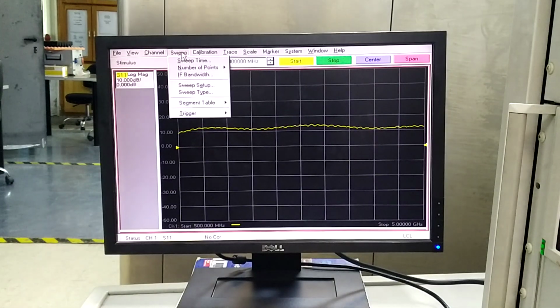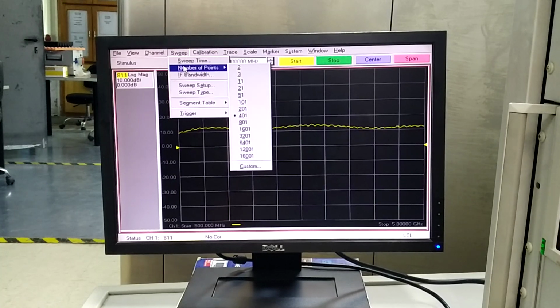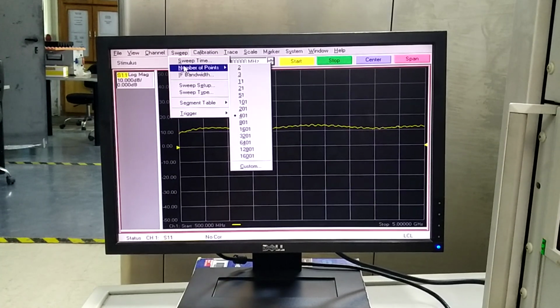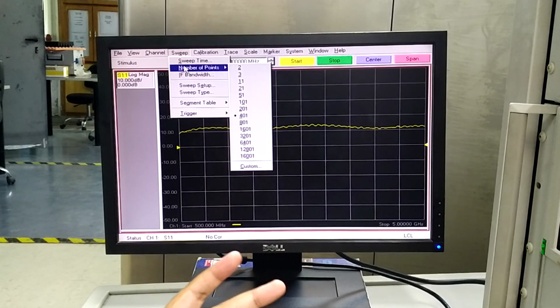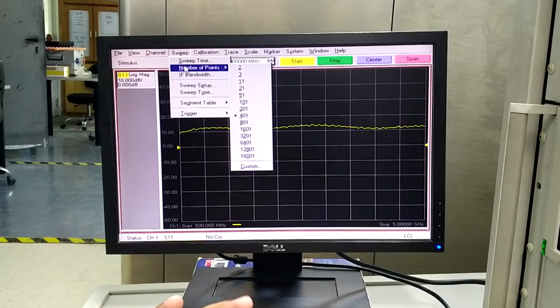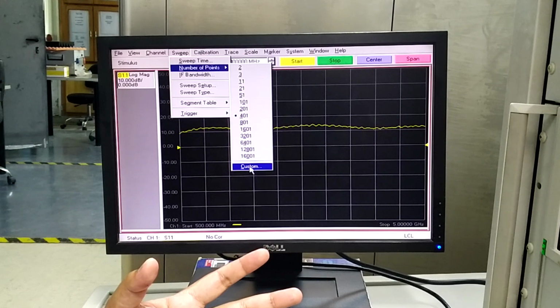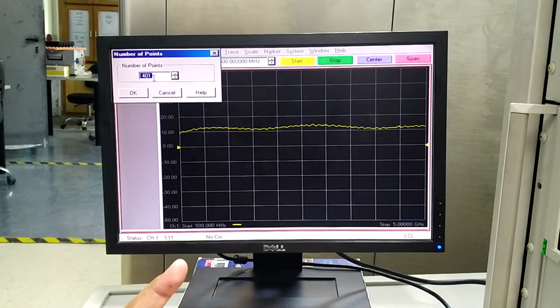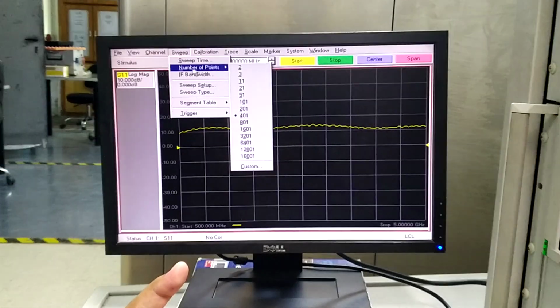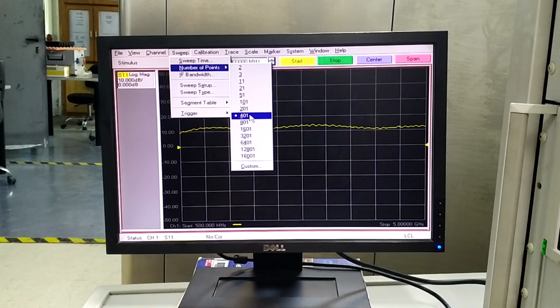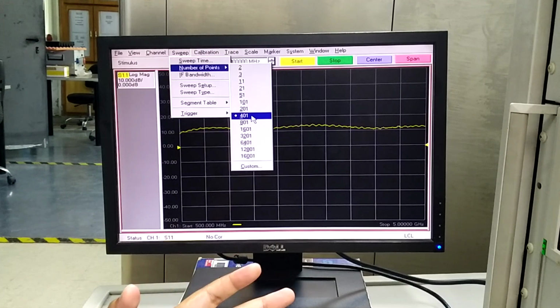We keep it OK. Now the next important thing is how many points you have between 500 megahertz and 5 gigahertz. Theoretically there are an infinite number of points between 500 megahertz and 5 gigahertz. However, in real life there's always some finite number of points. You can see there's a list of numbers of points available here, from 2 to 16,001 points. You can select any point count in between, or if you think your number is not available in the list, you can go to the custom option and enter any number you would like. However, for our case, we will put a fixed number of points between 500 megahertz and 5 gigahertz and select, let's say, 401 points between these two frequency ends. So now the VNA will perform the measurement from 500 megahertz to 5 gigahertz with 401 points in between them.